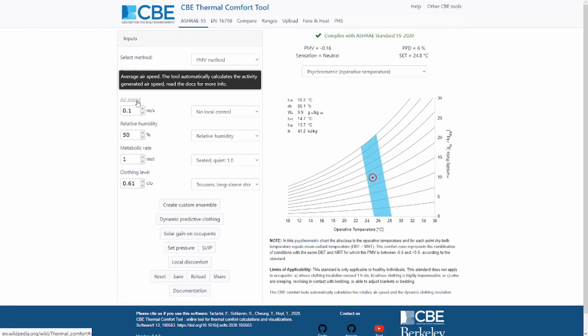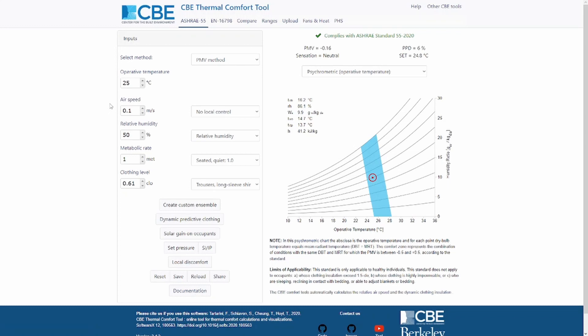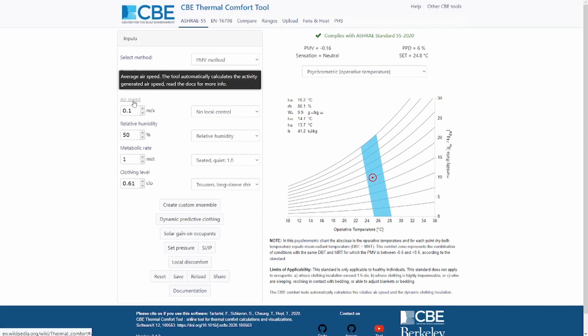On the other hand, if the person is standing, then you measure the airspeed at three different heights which are 0.1, 1.1 meters, and 1.7 meters, and again you should average these values. The same is true also for the air temperature and the mean radiant temperature, which should also be measured at three different heights.